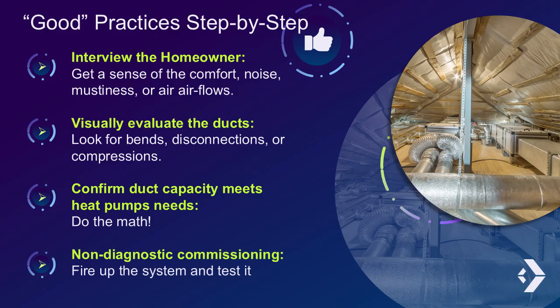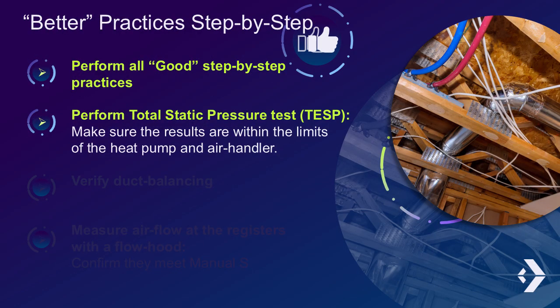Finally, perform non-diagnostic commissioning. Once you're confident the duct system will work, or you've adapted some element to make it work, install the heat pump and fire up the system at full fan power. Confirm that airflow is reaching all the registers, and check for any signs of obvious leakage into the attic, crawl space, or basement. Now let's move on to the next level, better practices for duct retrofitting.